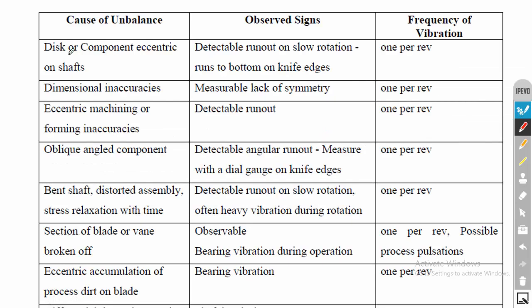There are other reasons for unbalance as well: a disc or component being eccentric on the shaft; dimensional inaccuracies, perhaps in the blades; eccentric machining or forming inaccuracies — for example, if a blade has a hole to fix it to the shaft with some eccentricity, it will produce unbalance. An oblique-angled component — if the component is not perfectly 90 degrees — will also produce unbalance. Then a bent shaft.